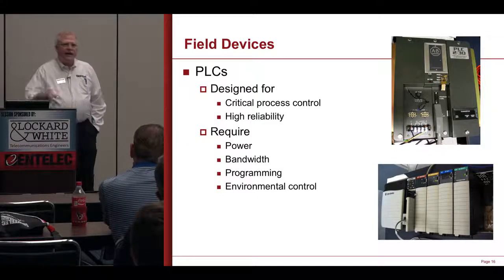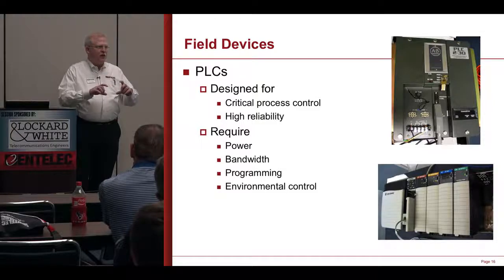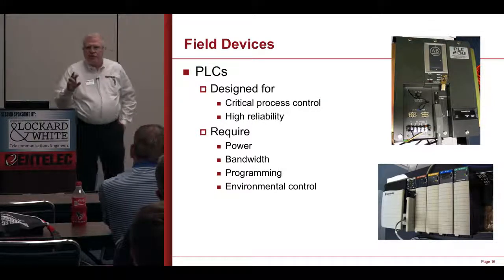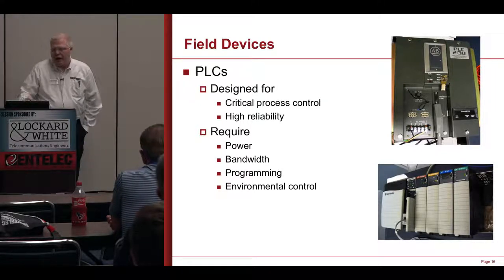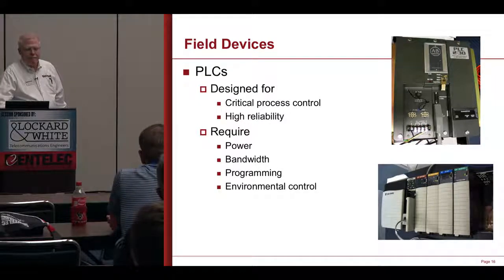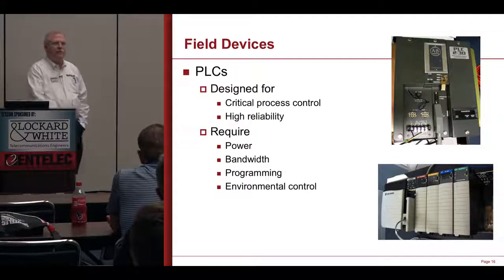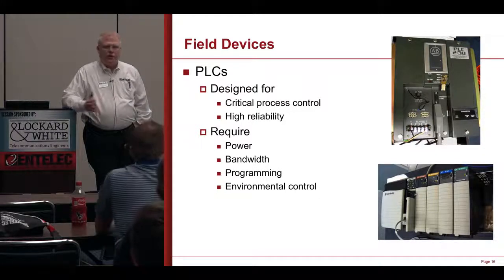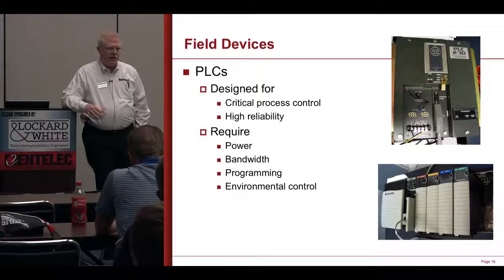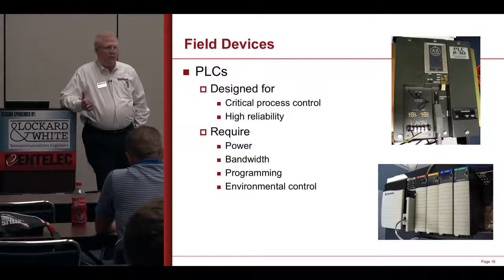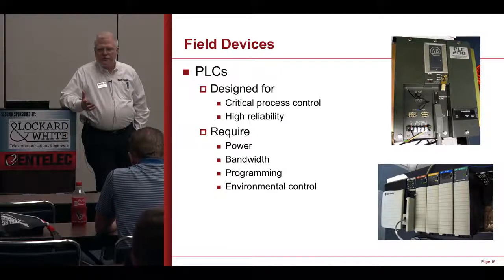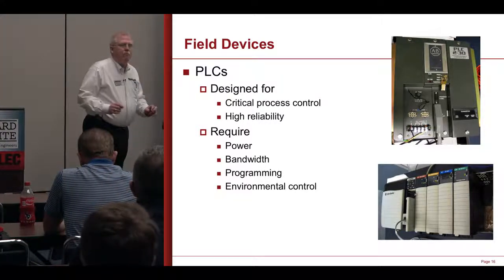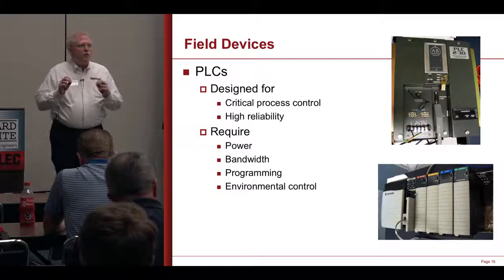PLCs require bandwidth — I need a wideband communications network behind the PLC to the remote IO components. They have to be programmed and need environmental control. There are more forgiving PLCs like the Allen-Bradley Micro, but the bigger stuff used to run a gas extraction facility requires some kind of environmental control — generally you're putting them in a building with air conditioning, probably with AC power and maybe battery backup. They're a lot more capable, but way more expensive to deploy.